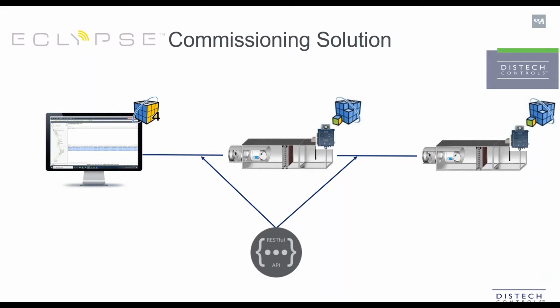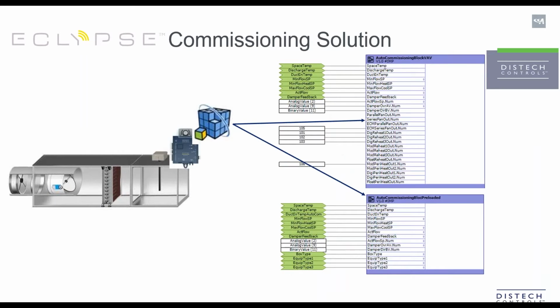First building block of the ECLYPSE Commissioning Solution is the Edge Analytics. ECLYPSE Edge Analytics testing sequences are executed at the device level in ECGFX program. If you are using the preloaded application, you have nothing specific to do at this stage. If you are using your own application, make sure to add the custom block from the Productivity Enhancing Tools version 3.7 to enable your controllers for Edge Analytics.